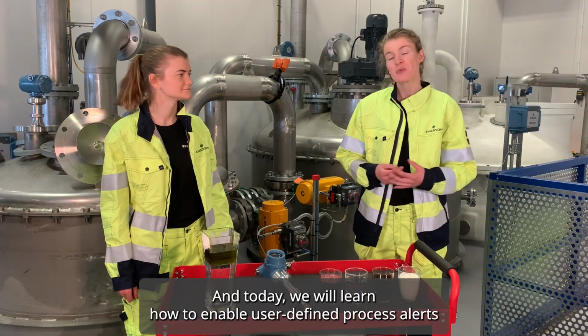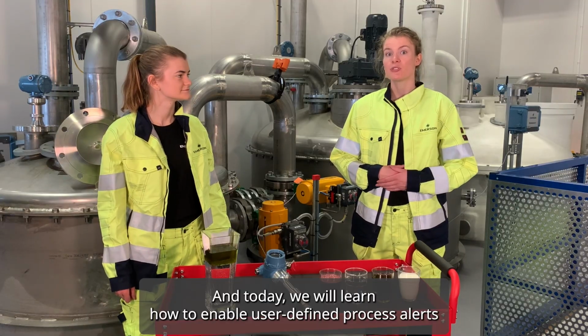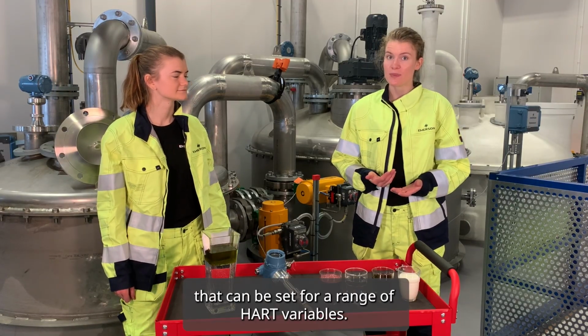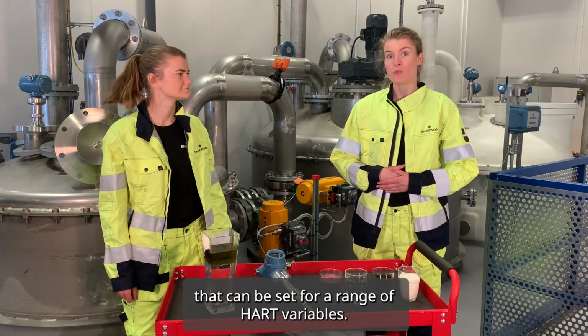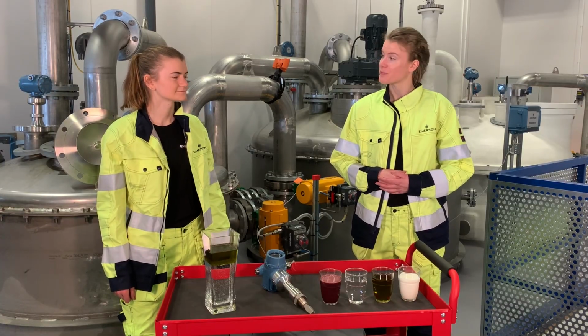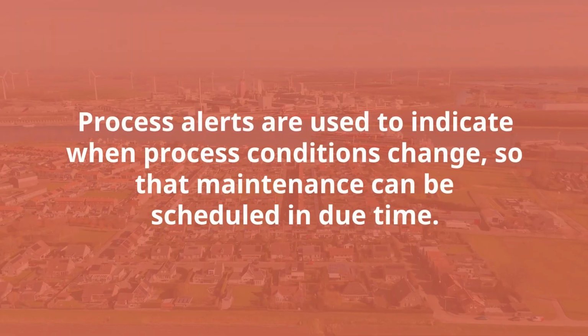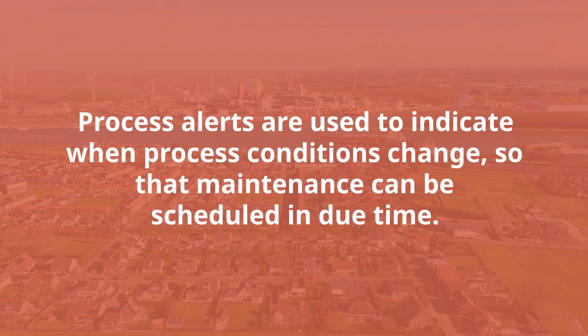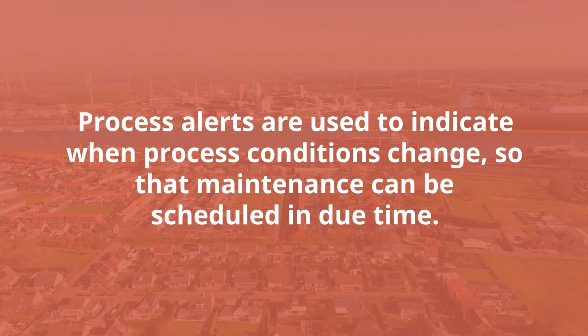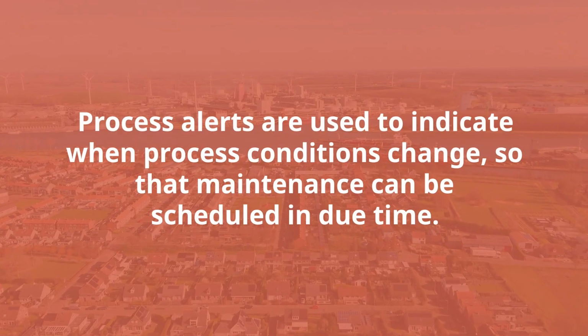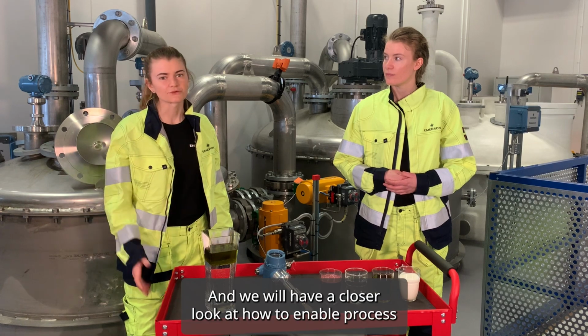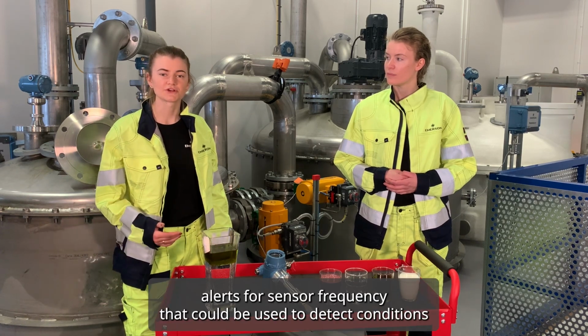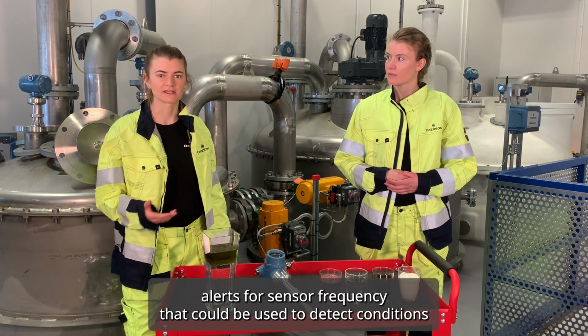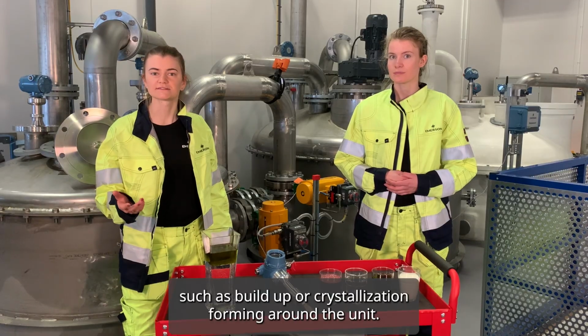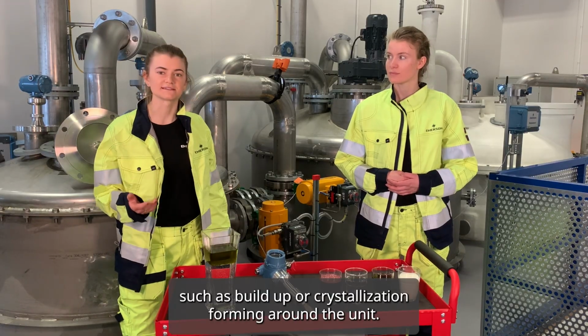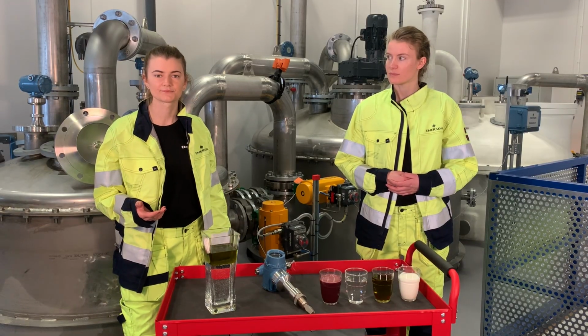And today, we will learn how to enable user-defined process alerts that can be set for a range of HART variables. Yes, so process alerts are used to indicate when process conditions change, so that maintenance can be scheduled in due time. And we will have a closer look at how to enable process alerts for sensor frequency that could be used to detect conditions such as buildup or crystallization forming around the unit.